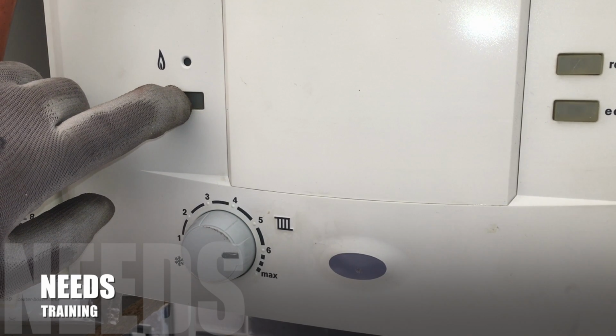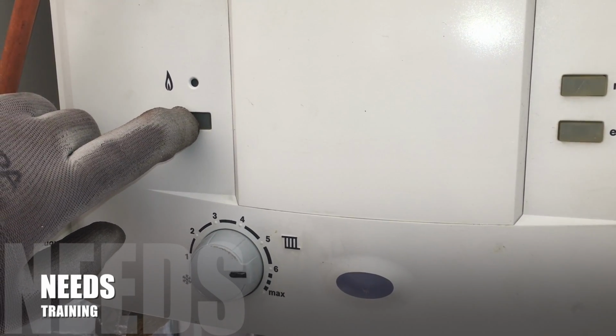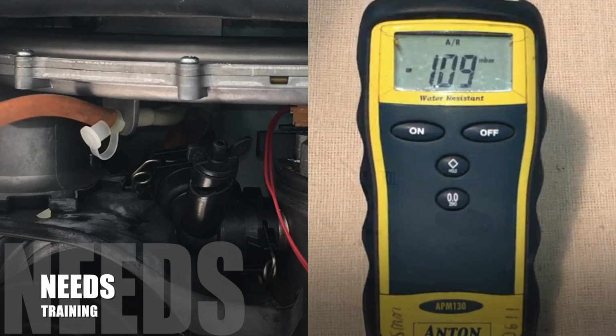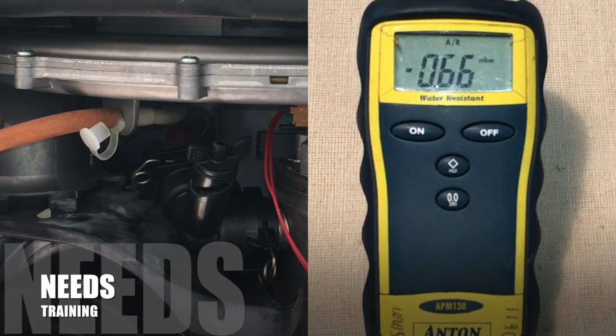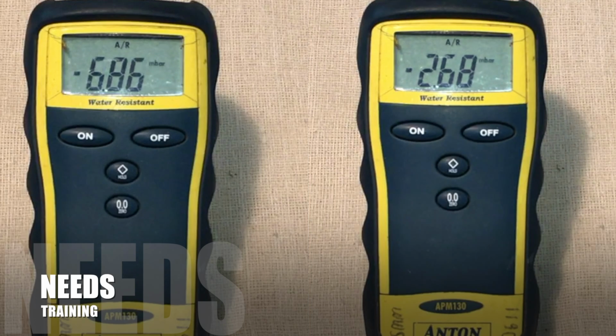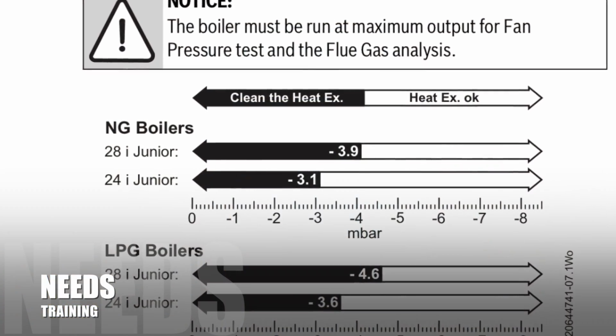Push the spanner button to enter engineer's mode. The orange light will appear. Turn the heating controls to max. Using a manometer, you are looking for a negative pressure reading greater than 3.9. All appliances have different negative pressure readings, as you can see in this table.